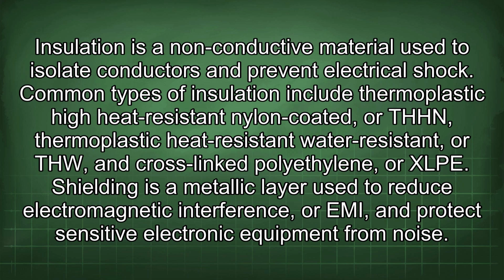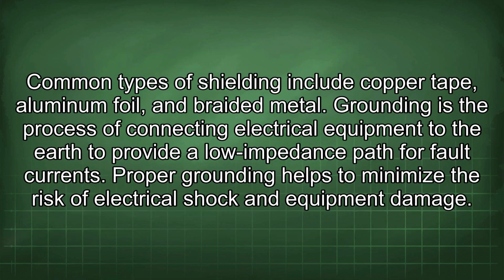Insulation is a non-conductive material used to isolate conductors and prevent electrical shock. Common types of insulation include thermoplastic high heat resistant, nylon coated, or THHN, thermoplastic heat resistant, water resistant, or THW, and cross-linked polyethylene, or XLPE. Shielding is a metallic layer used to reduce electromagnetic interference, or EMI, and protect sensitive electronic equipment from noise. Common types of shielding include copper tape, aluminum foil, and braided metal.